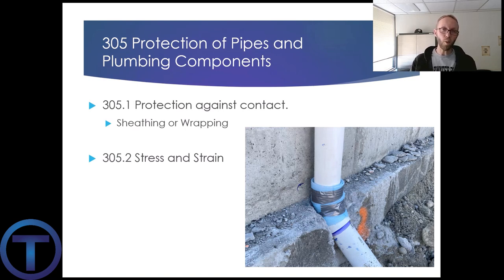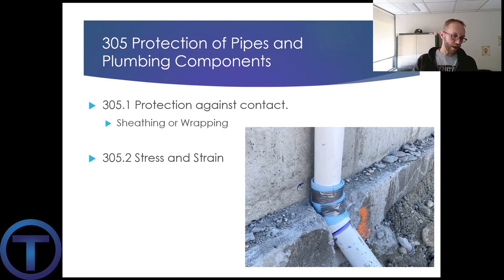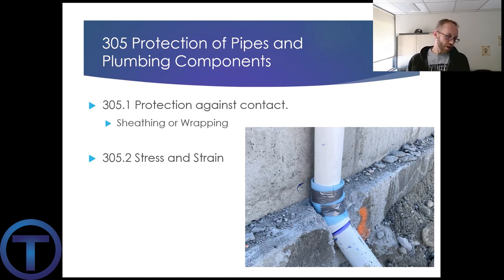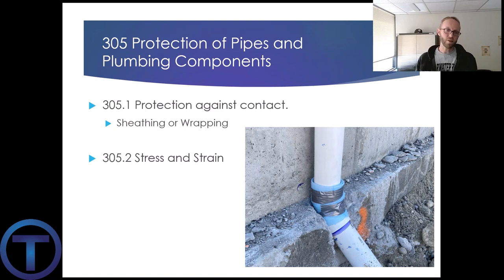When a non-ferrous metal like copper comes in contact with a ferrous metal and water moves through it, you'll have electrolysis happening — the electrons start to eat away at the copper. For that reason, it says metallic piping, except for ferrous metals like cast iron, ductile iron, and galvanized steel, shall not be placed in direct contact with steel framing members, concrete, or cinder block. We're just trying to protect those metals — particularly copper — from corrosion.